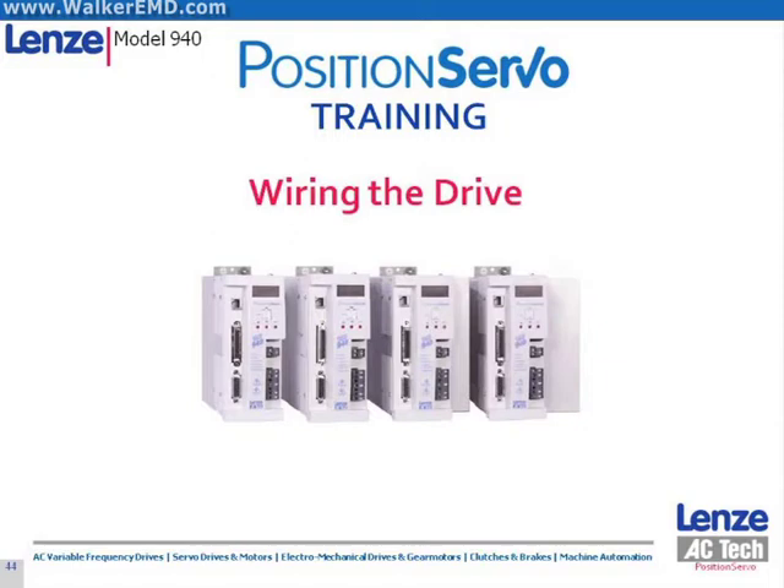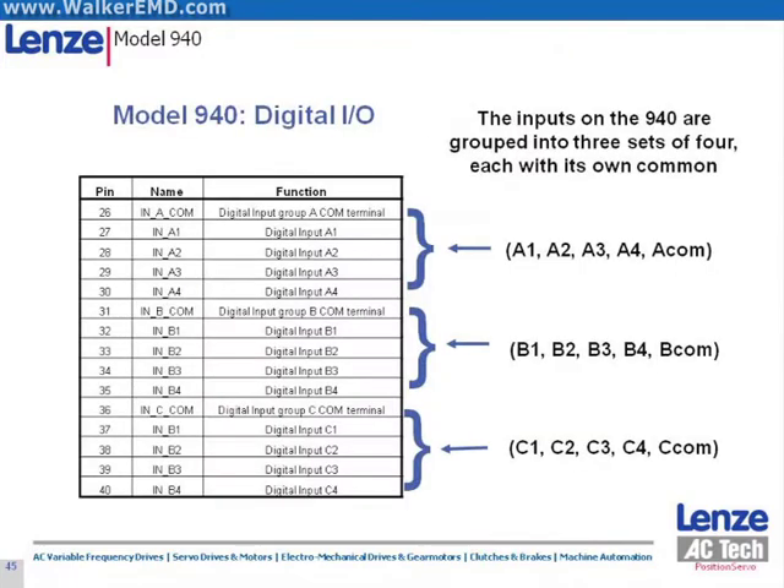In this section, we will discuss field wiring for Lenze's position servo drives. The 12 digital input signals of the position servo are grouped into three groups of four, each group having its own common. The I/O can accept 5 to 24 volt DC signals; however, all I/O within a given group must be of the same voltage.